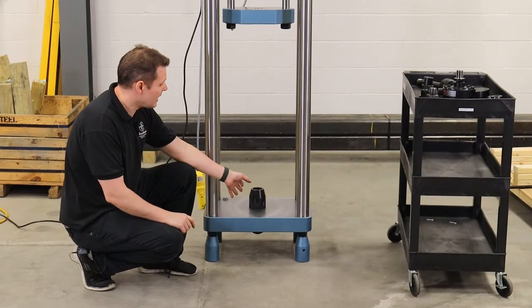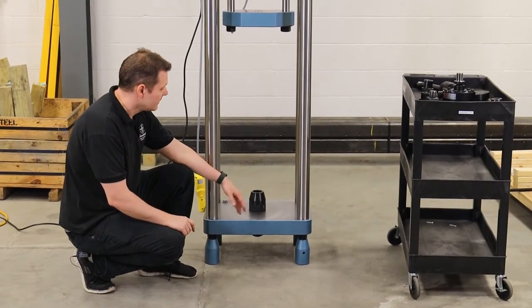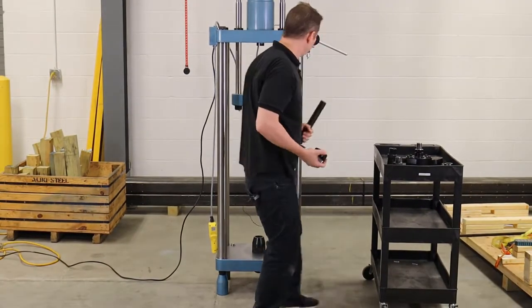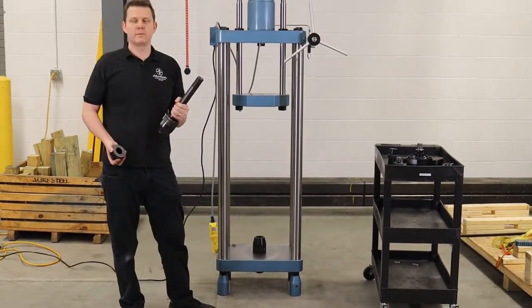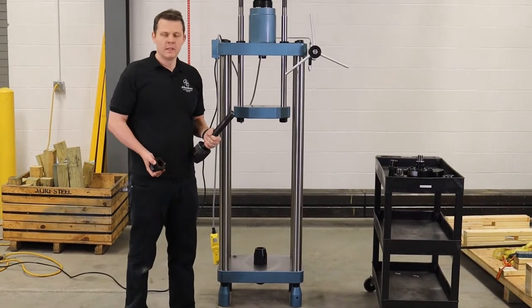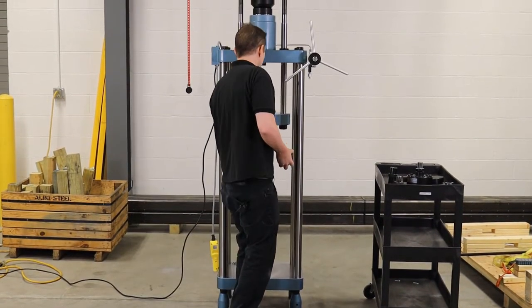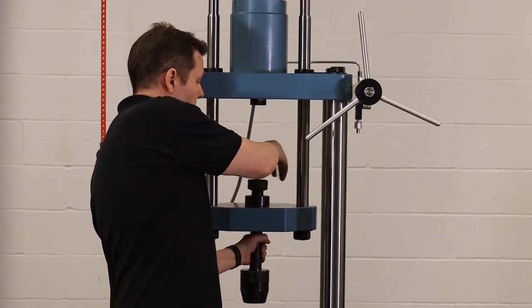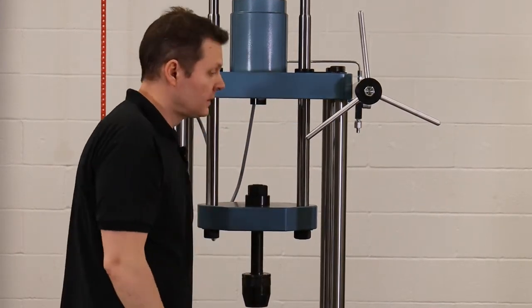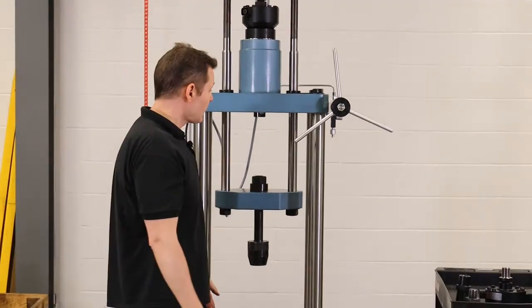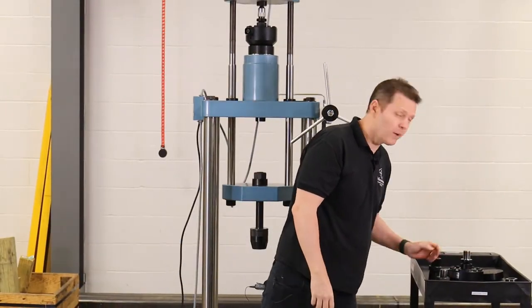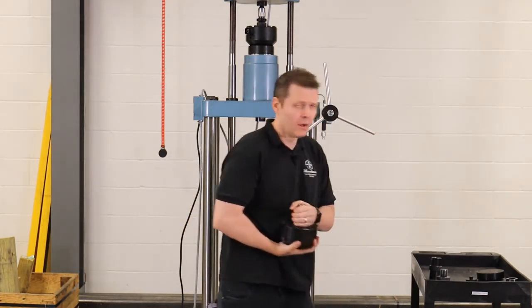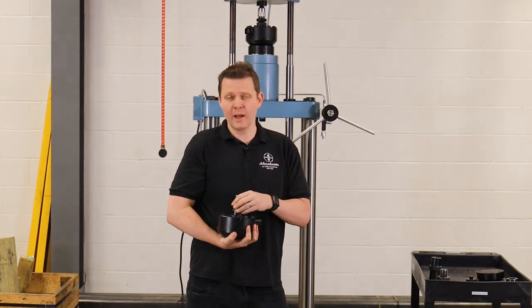So now we have the bottom adapter in that's tight, and like I said people just leave that in the machine, really no reason to take it out. Then we have a top one, this rod is usually typically two sizes, long and short, there's a spherical in here and we just thread the nut on. Now we're going to mount the load cell. You want to know what end is the live end and the dead end. On this load cell the live end is this way so we want to face that live end facing the force.